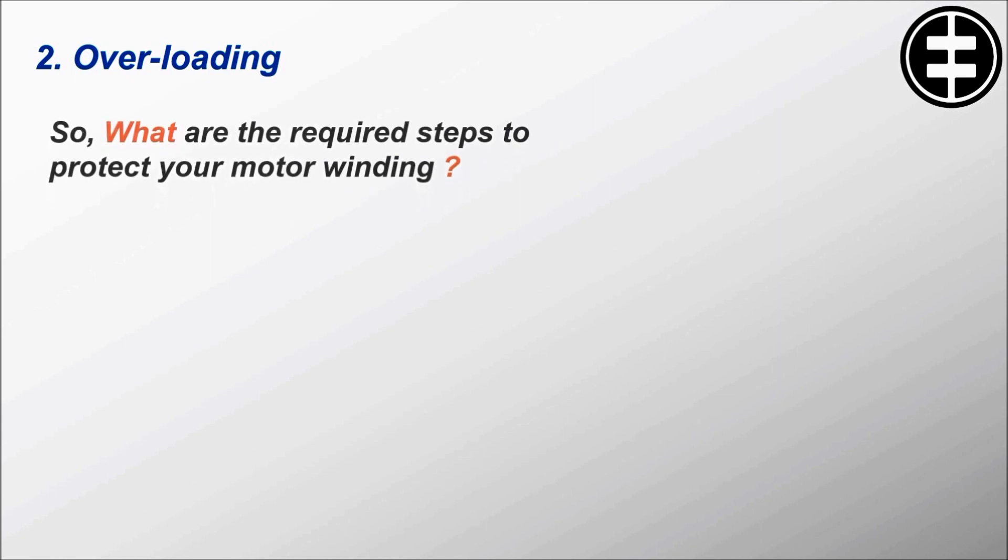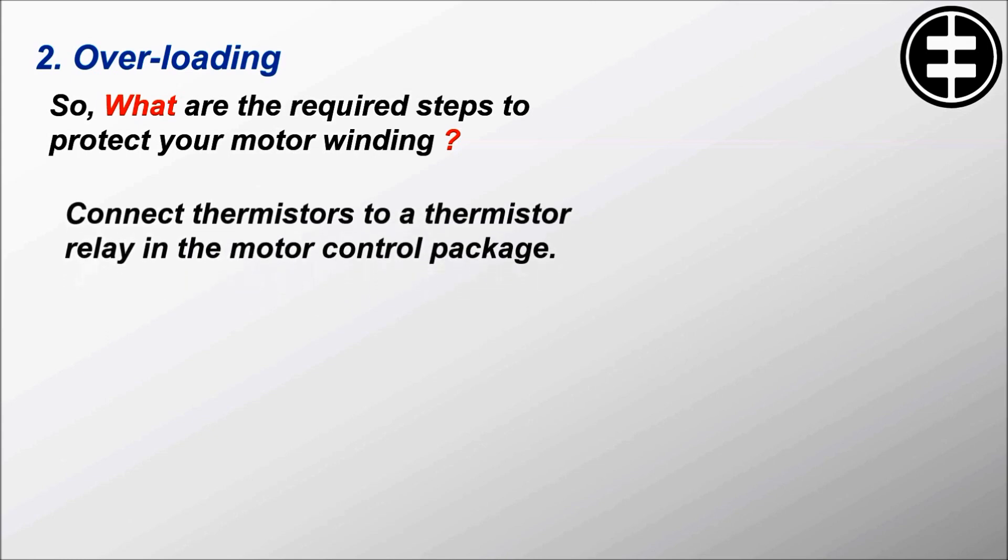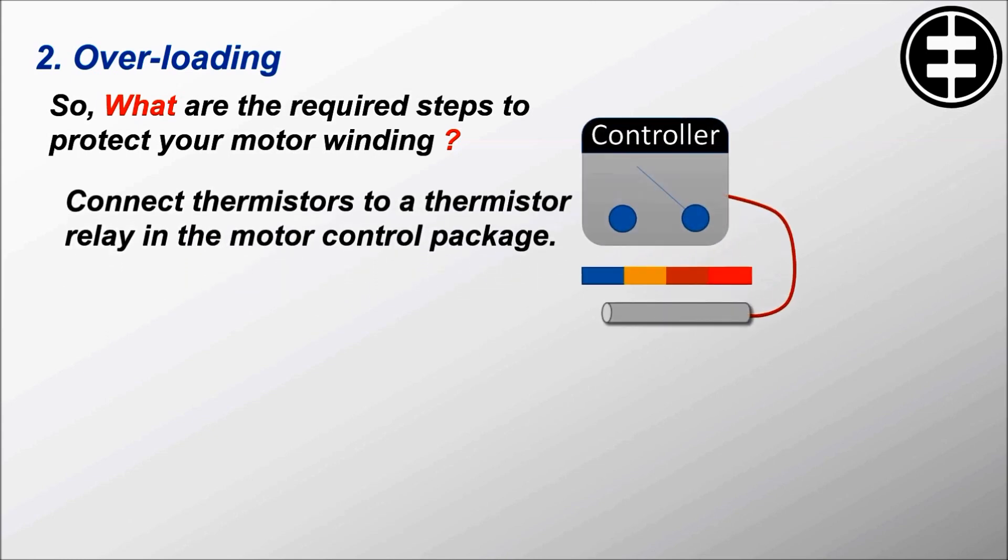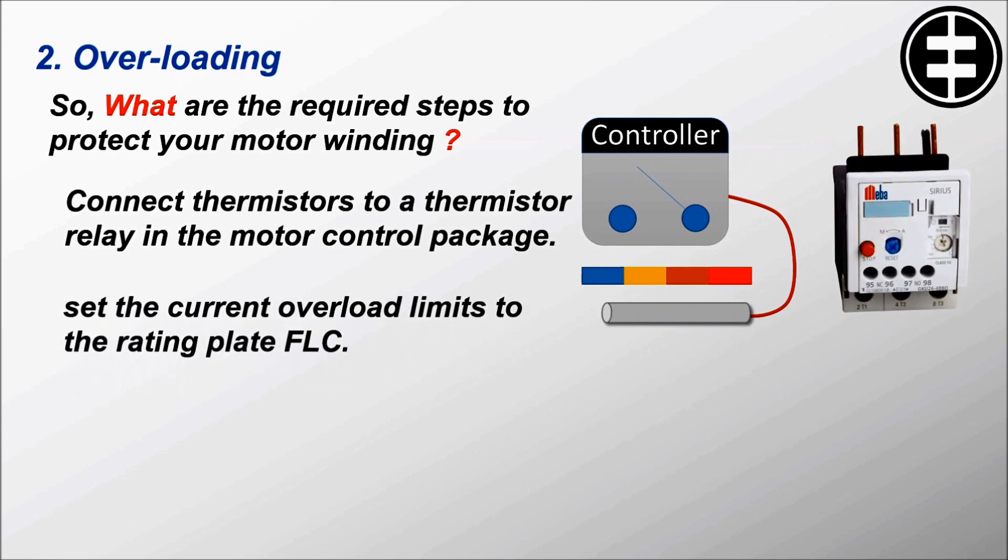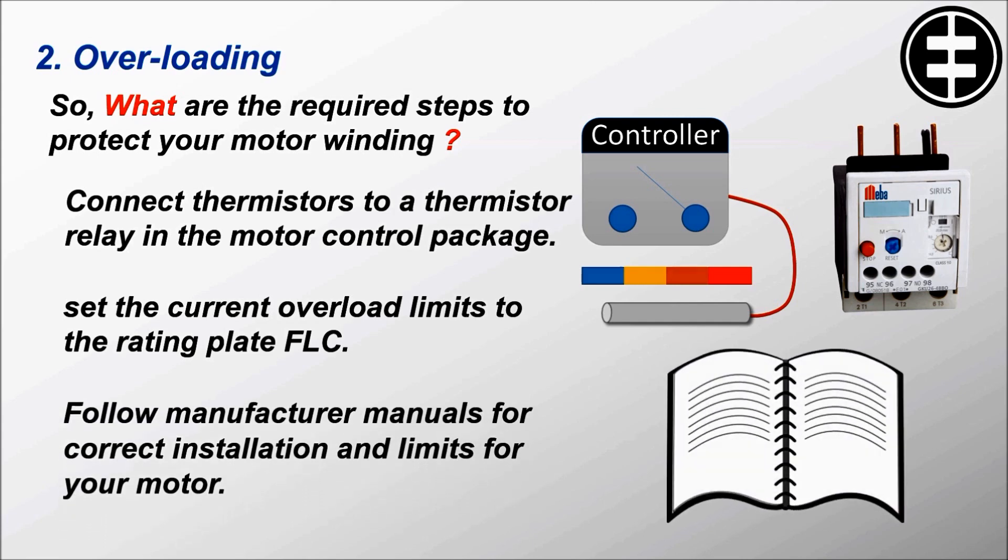So what are the required steps to protect your motor winding? 1. Connect thermistors to a thermistor relay in the motor control package. 2. Set the current overload limits to the rating plate full load current. 3. Follow manufacturer manuals for correct installation and limits for your motor.